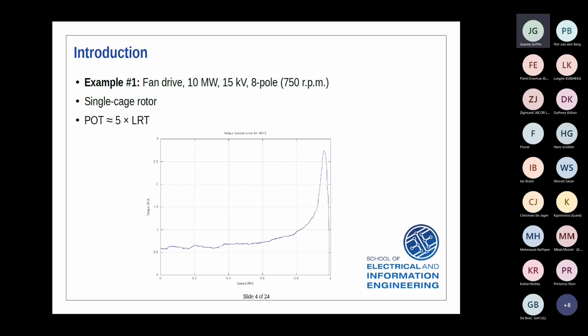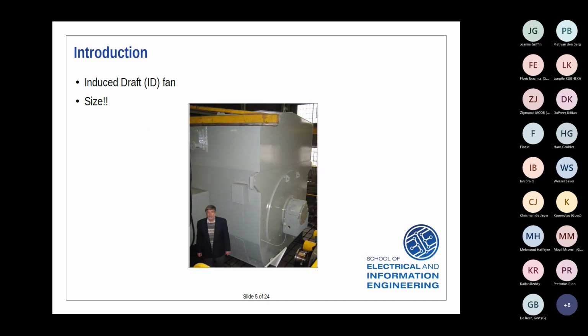In terms of the relationship between torque and slip, you can see here there's a very clear 1/S function on this range of the slip from 0 to 1. And on the right-hand side, after the pull-out torque, we have a proportional to S function, so almost a linear straight line down, basically to 0. Typically the load, in this case a pump or a fan, would have a square law which would intersect over here. The operating point is over there. So that's a classic single cage machine.